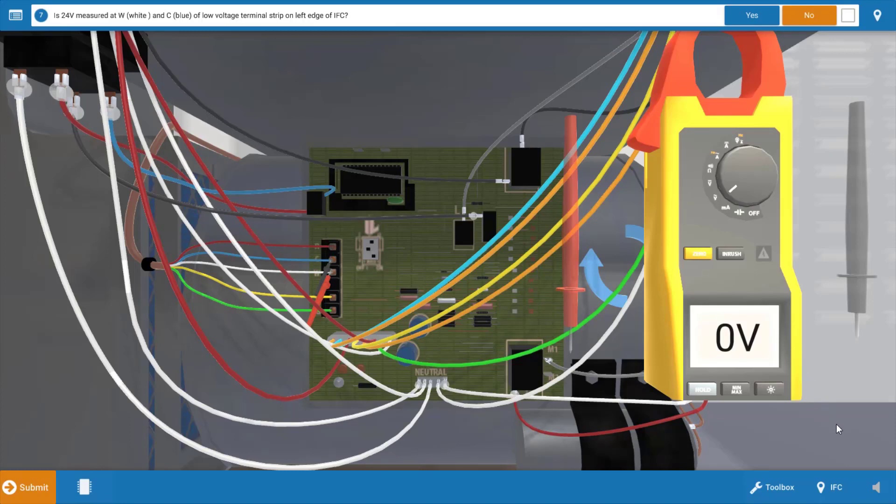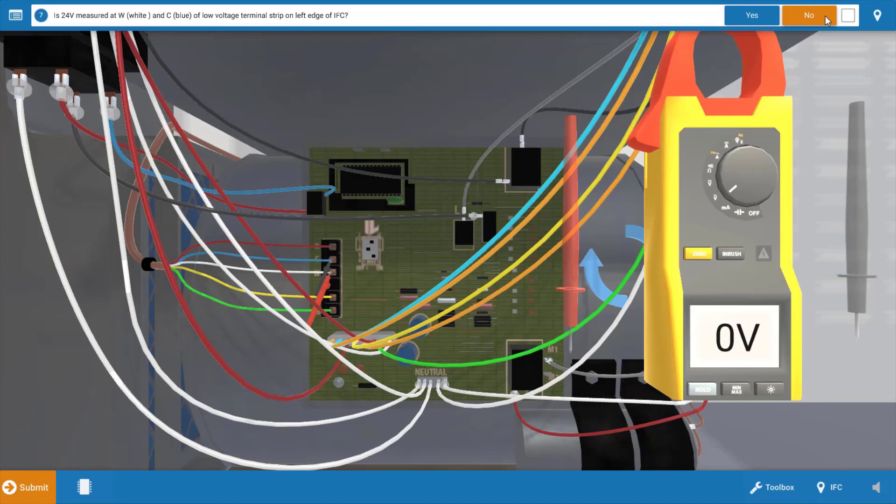So we had power going to the thermostat, we have no power coming out of it back to the IFC. So the IFC is not being signaled to start the sequence of operations. So we're going to click no on the procedure guide.